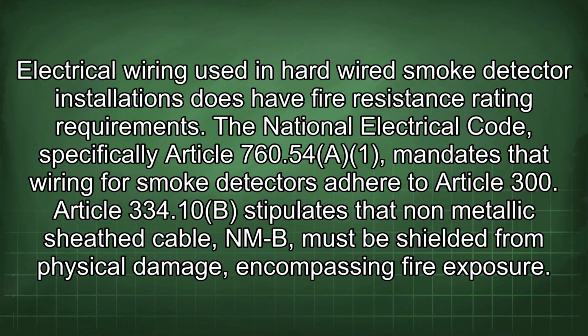Electrical wiring used in hard-wired smoke detector installations does have fire resistance rating requirements. The National Electrical Code, specifically Article 760.54 A1, mandates that wiring for smoke detectors adhere to Article 300. Article 334.10(B) stipulates that non-metallic sheathed cable, NMB, must be shielded from physical damage encompassing fire exposure.